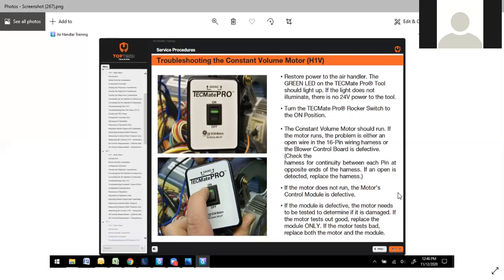That's how it usually is, but you can replace just the module on these as well, if the motor's good. And I've only seen a handful, maybe 6 motors that were truly defective. Every other time it's been the module. But there's a way you can check the motor as well.